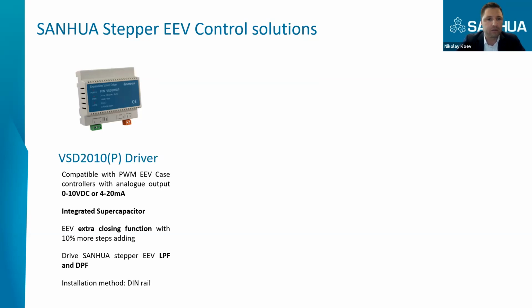It is important to mention that this driver is equipped with an integrated ultracapacitor, so there is no need to add an additional power supply. We also have an extra closing function, which means that on receiving a certain low voltage signal, the controller will close the valve completely and add 10% more steps. If the EEV has 500 steps, the controller will add an additional 50 steps to ensure that the valve is completely closed.